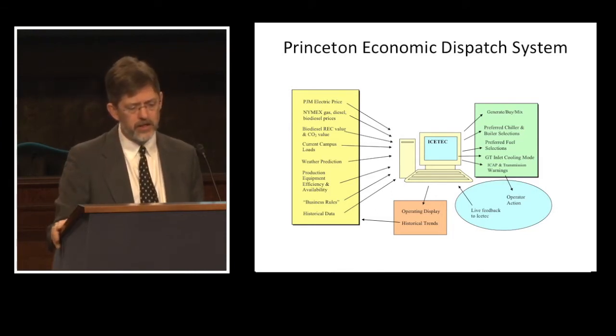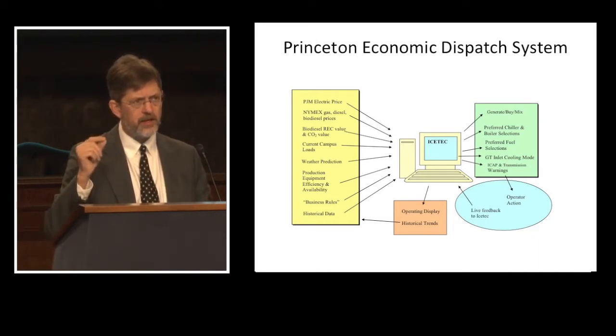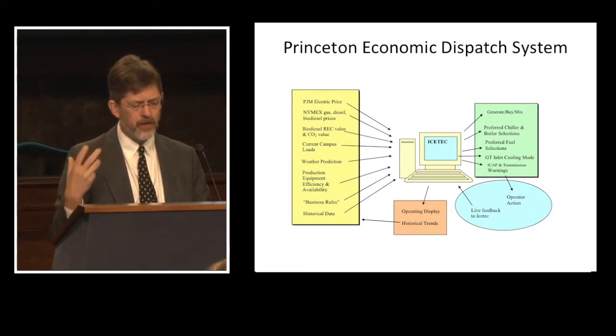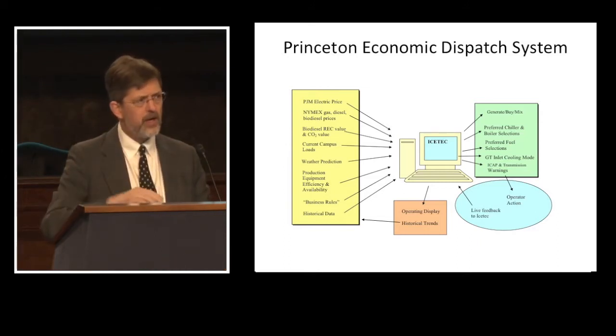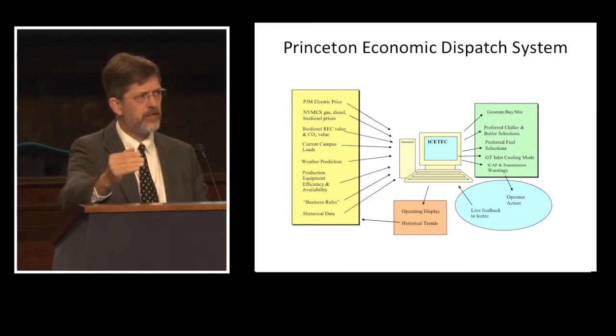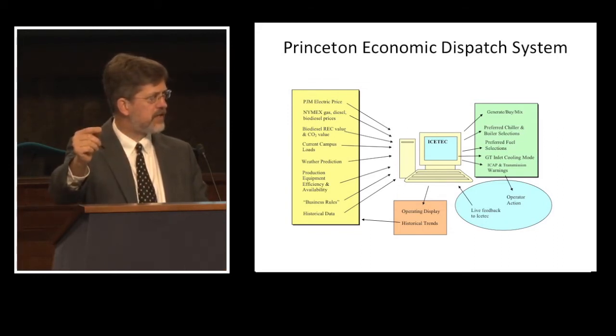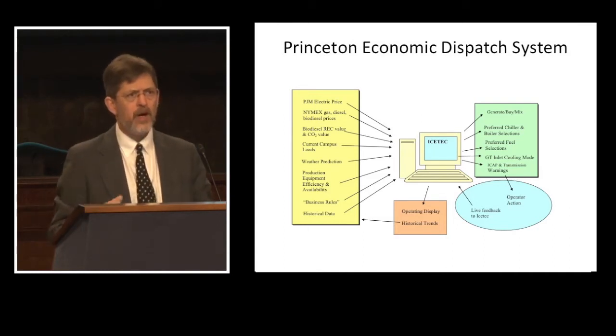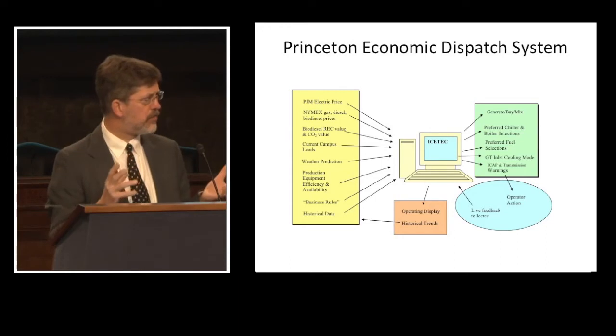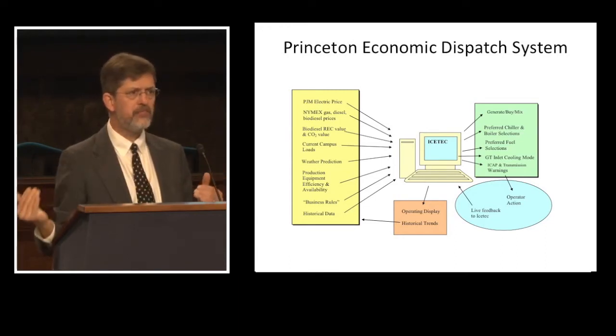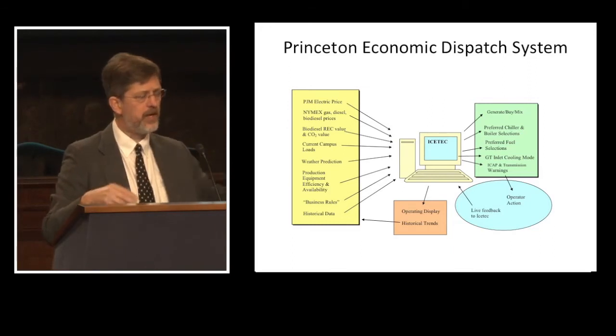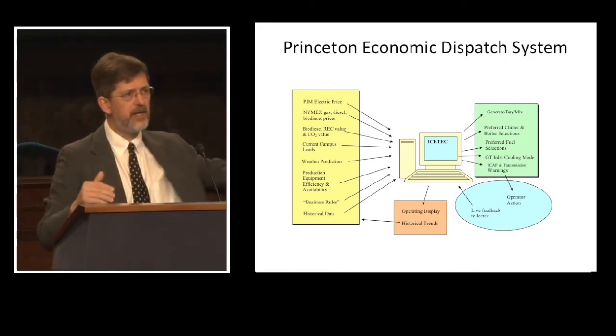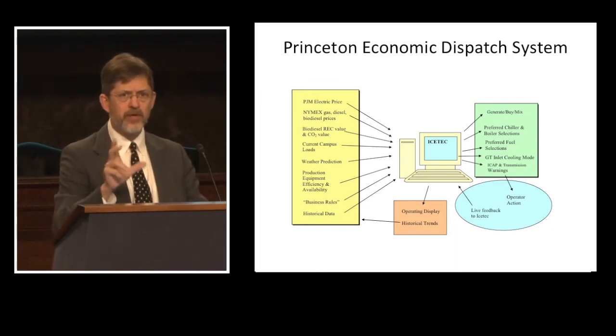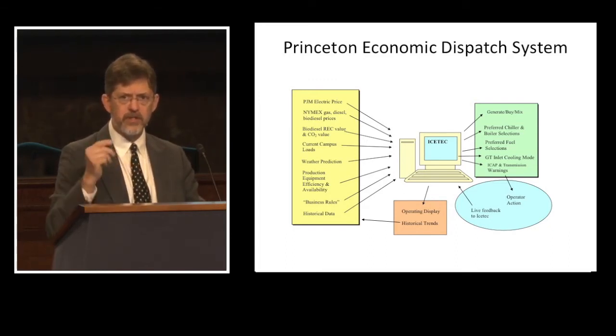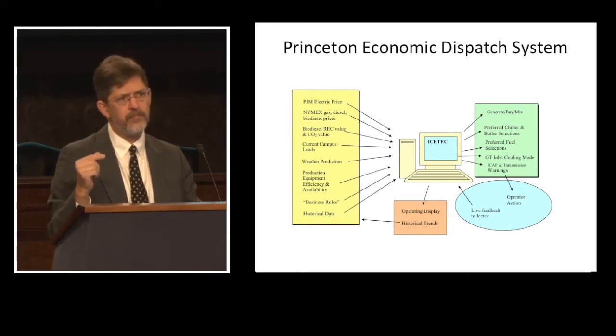We take the Pennsylvania, Jersey, Maryland interconnection electric price, the NYMEX price for natural gas and diesel fuel. We measure the current campus loads and the weather prediction, looking forward 24 hours in great detail, looking forward 7 days in less detail. And rather than just taking engineering design numbers for the equipment we're operating, we actually measure BTUs in and kilowatt hours out, kWhs in and ton hours of cooling out. We measure in real time how the equipment performs so we know exactly which piece of equipment to call on in real time.